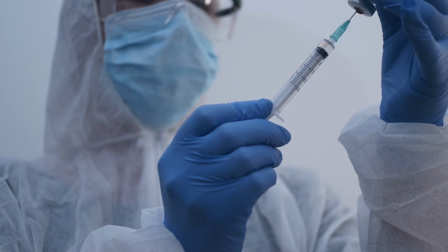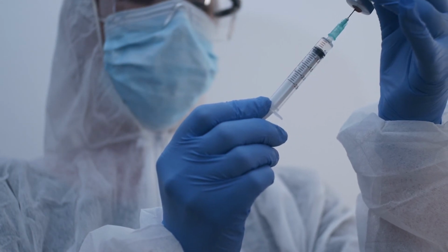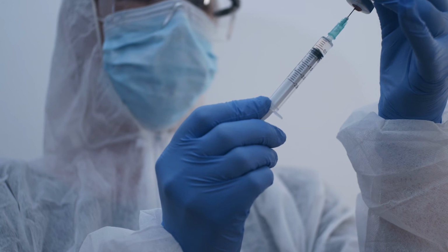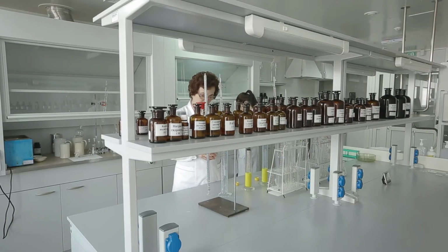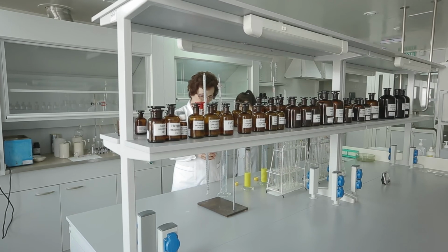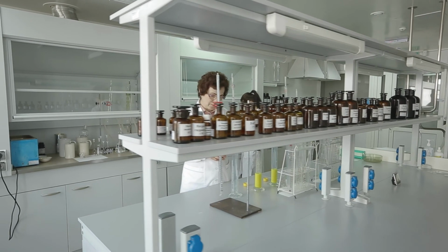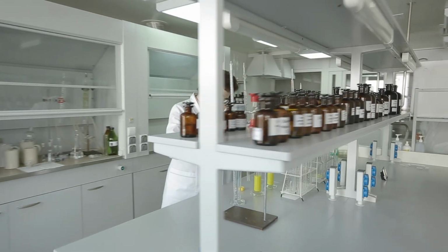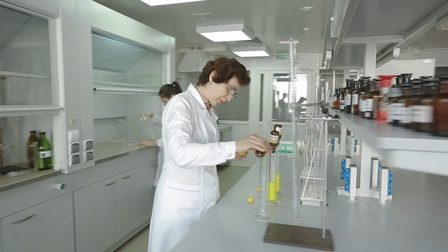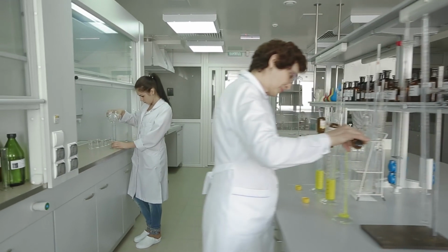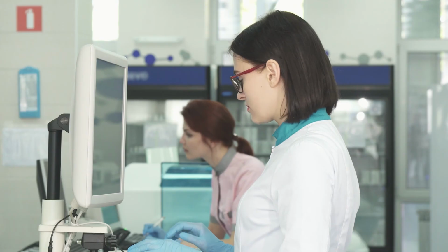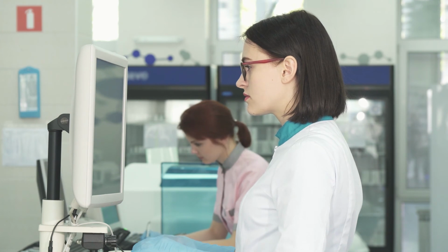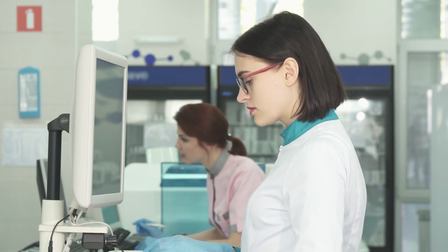Small, inadvertent variations in injection volume occur whenever injections are performed manually since it is difficult to fill a syringe to an exact volume. Experiments have shown that reading a scale is more accurate than trying to fill a syringe.